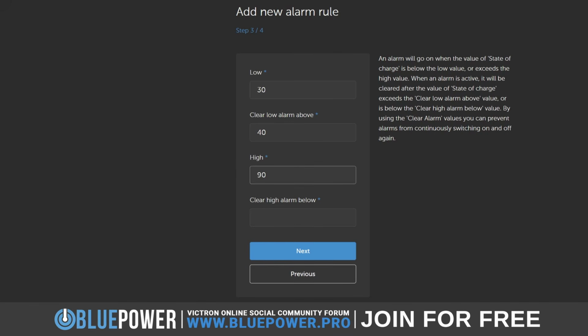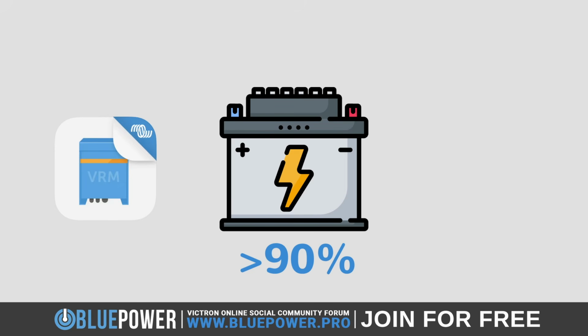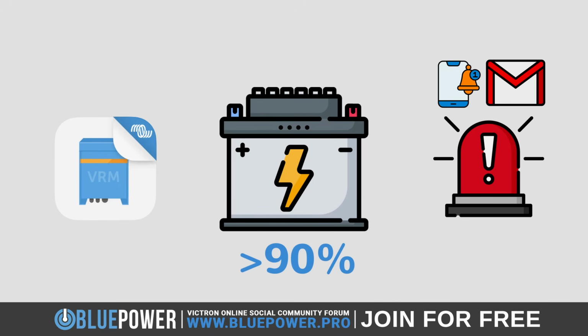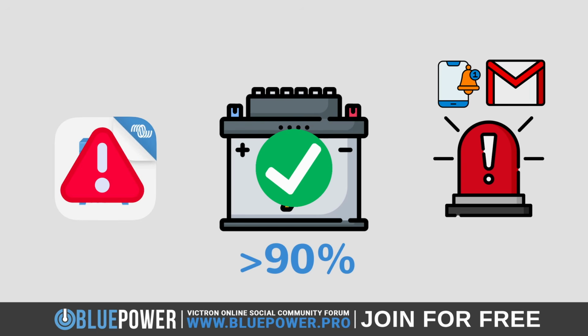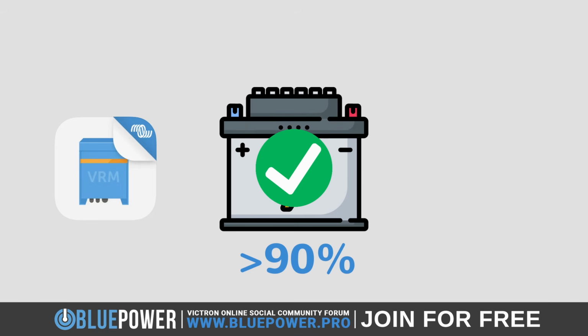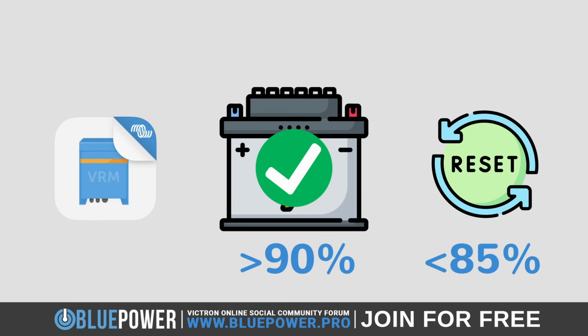If I were to enter a high value of 90%, the VRM would send me an alert on my phone and email, while also creating a constant red warning in my VRM when my batteries reach 90% or more. But this is a good thing, so I don't really require a warning to tell me this. However, the biggest problem comes in the fact that in order to clear this warning, the battery has to dip below this value. In other words, it needs to discharge below, let's say 85%, in order for this warning to clear.